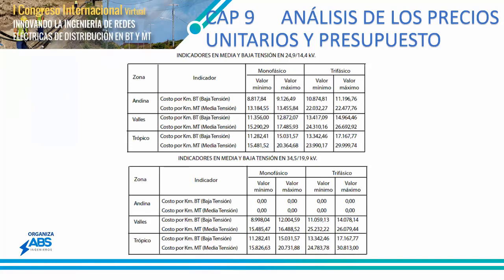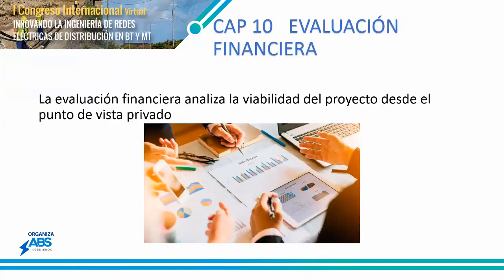Por ejemplo, en la zona andina, el valor máximo para una red trifásica es 22,500 dólares el kilómetro. Son indicadores que pueden variar, pero hacen una referencia muy interesante para estimar cuánto podría costarnos una red eléctrica de distribución en el área rural.